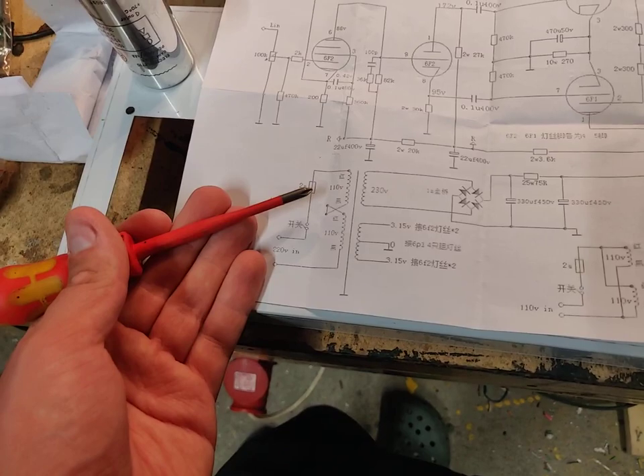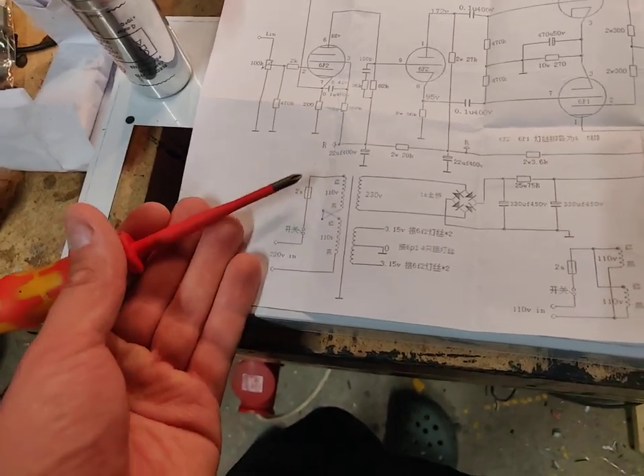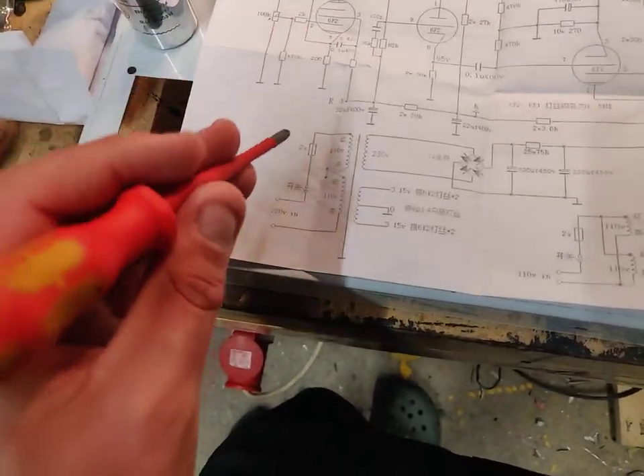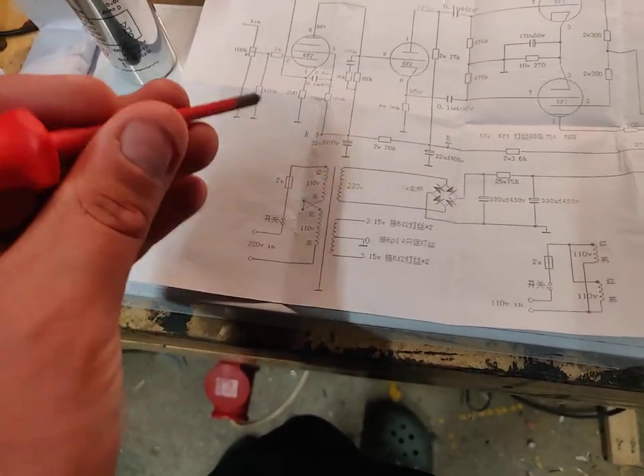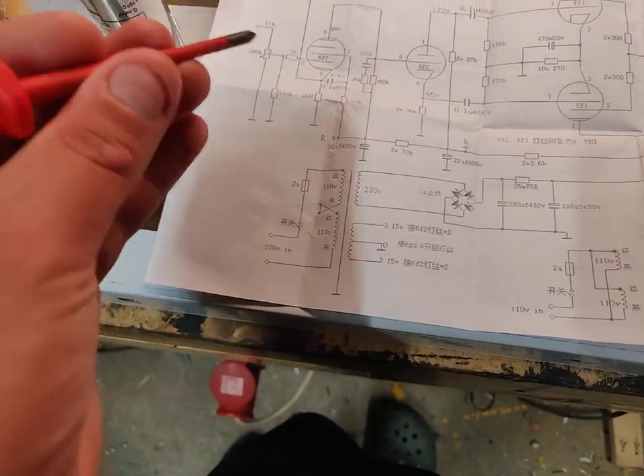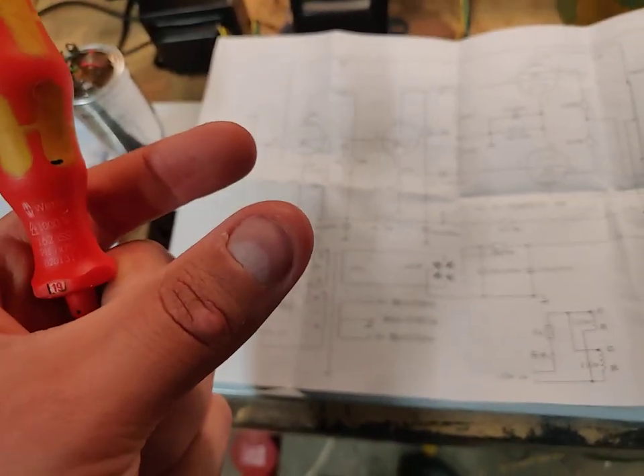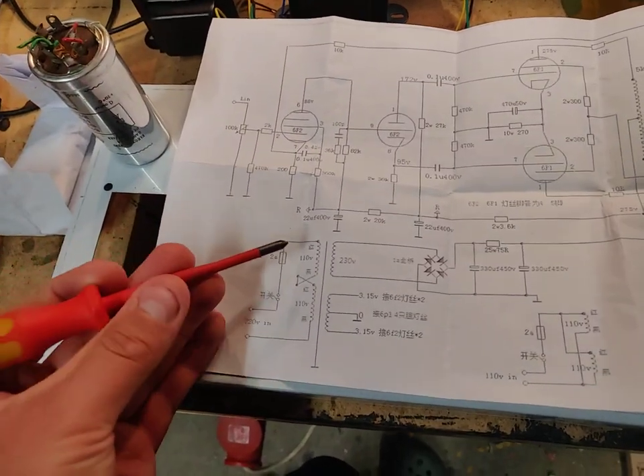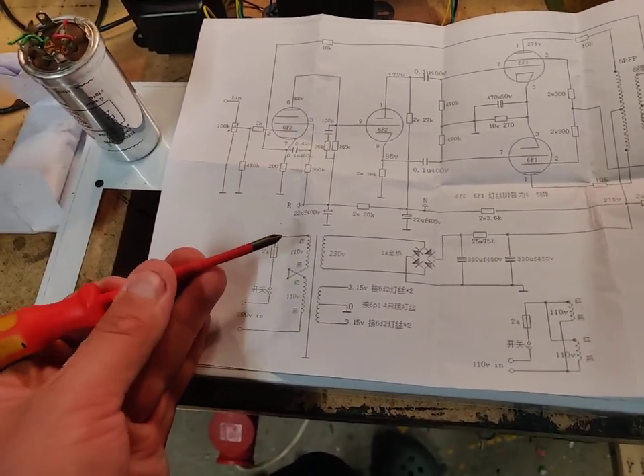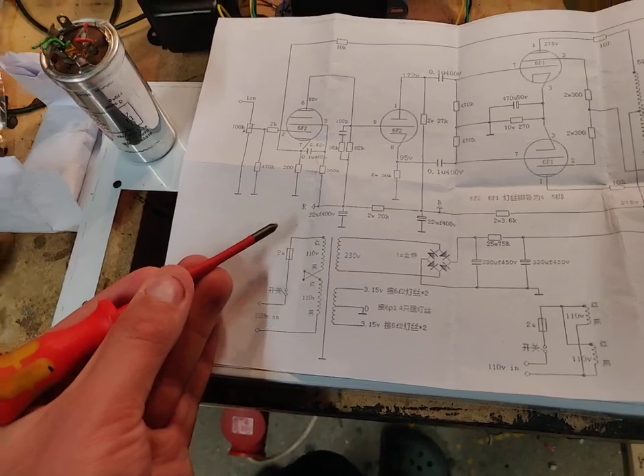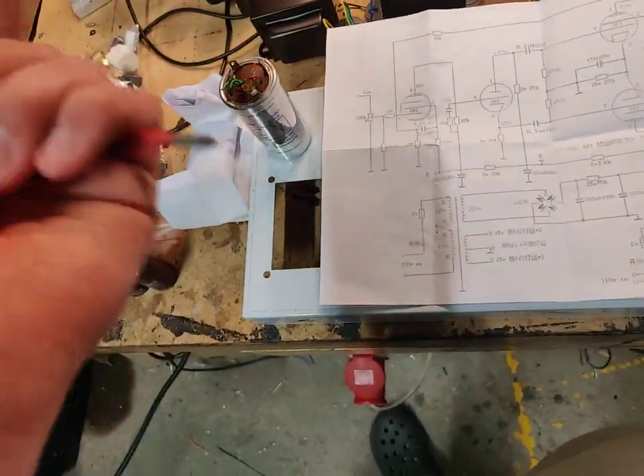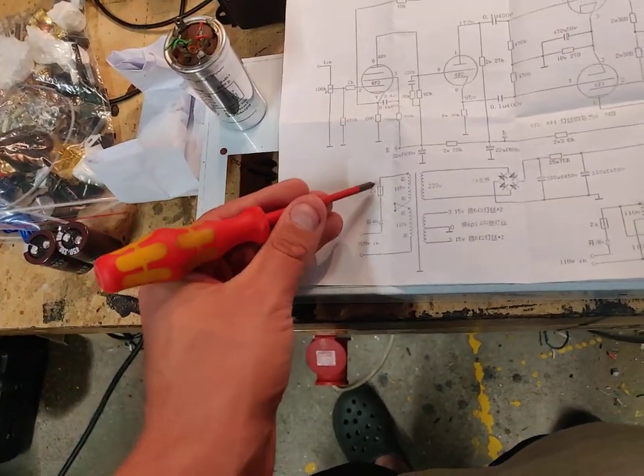You could put a slow blow, probably 1 amp, and you'll still be fine. Try and put the lowest value you can here, without running it right at the limit, because that can really stress the fuse. But get a fuse that's within 200 or 300 milliamps of the transformer rating. I will go with a slow blow for something like this, so it can handle the startup current.